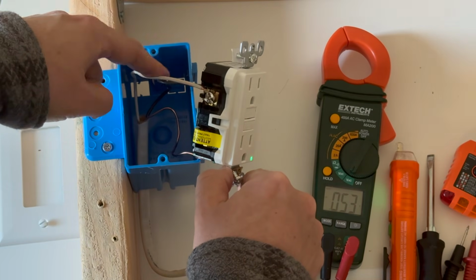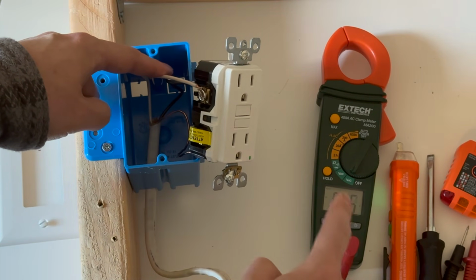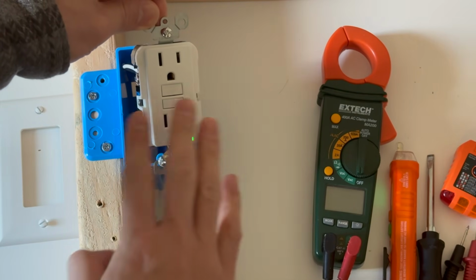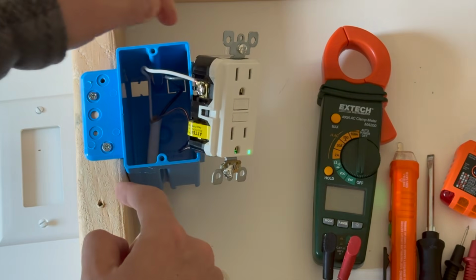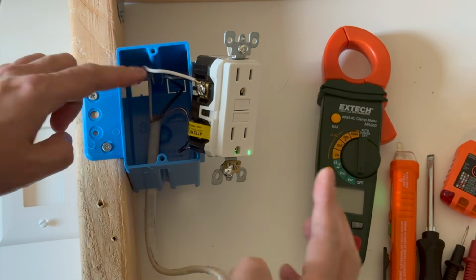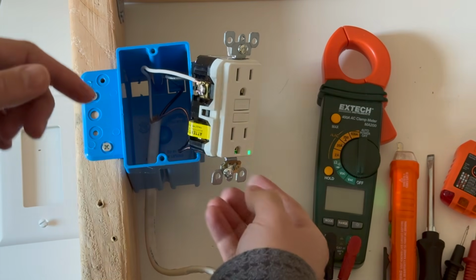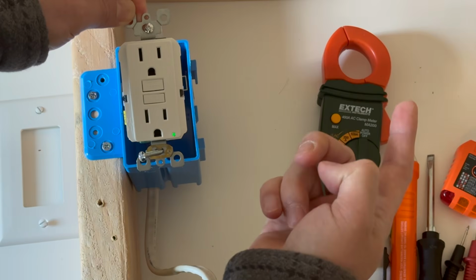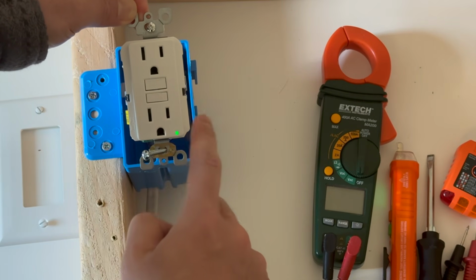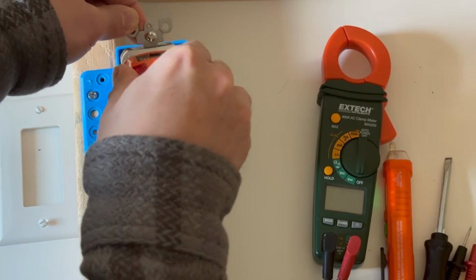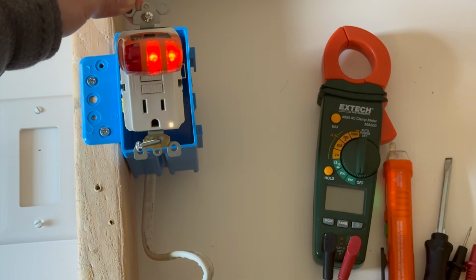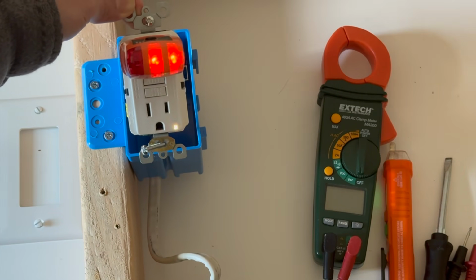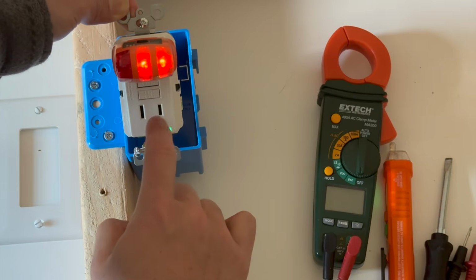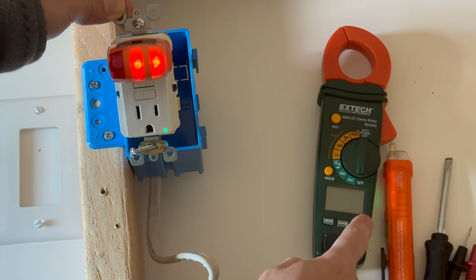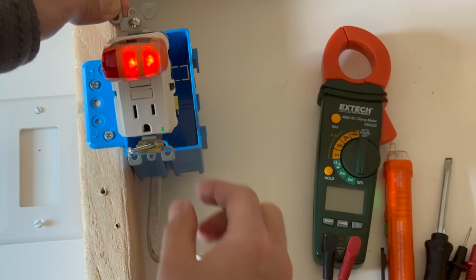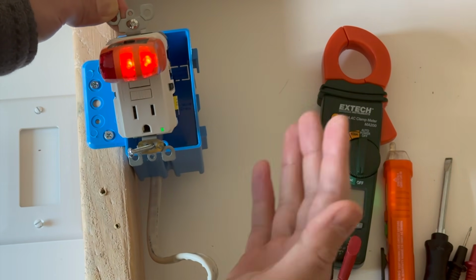But if you don't have a power coming here and multimeter reads 0, that means the problem is not here, at least until you have a power on these wires. Okay, so this is just a simple way of troubleshooting. And again, if GFCI, let's say outdoor, or if it's your garbage disposal, most likely this outlet is switched, just like in my case. Okay, so I'm able to turn it on and off because that circuit has to be switched for me. Okay, so if you have a dead outlet, GFI, and you're reading the terminals, you're getting 0 voltage, you might need to look for a switch, or you might need to go take a look at the breaker.